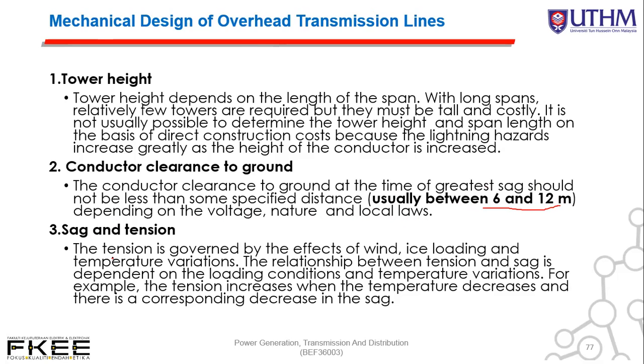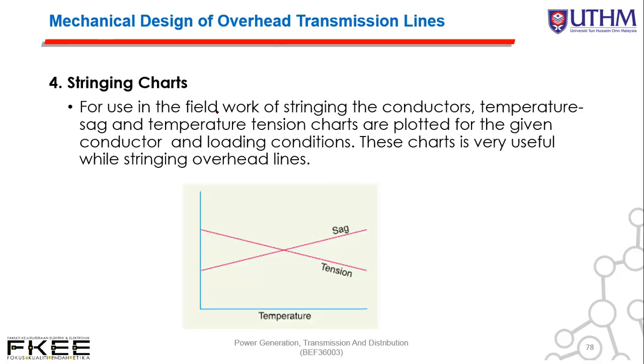Number three, sag and tension. The tension is governed by the effect of wind, ice loading, and temperature variation. So the relationship between tension and sag depends on the loading condition and temperature variation. For example, the tension increases when the temperature decreases, and there is a corresponding decrease in the sag. Stringing charts are also important for the mechanical design. For use in the field work of stringing the conductor, there are temperature-sag and temperature-tension charts. Temperature-tension charts are plotted for the given conductor and loading condition. This chart is very useful while stringing overhead lines. Basically we will use this chart between tension, sag, and also temperature.